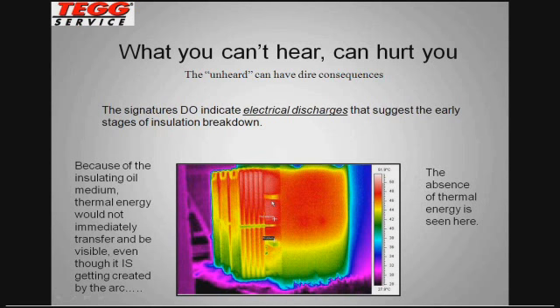This is the type of image we would like to see, even if arcing is going on, be it the time domain I showed you a moment ago, or a continual, more frequent arc within this type of unit. It would be quite some time before it would raise the temperature of the insulating oil enough for the infrared camera to be able to see it. And I hope that answers the question.